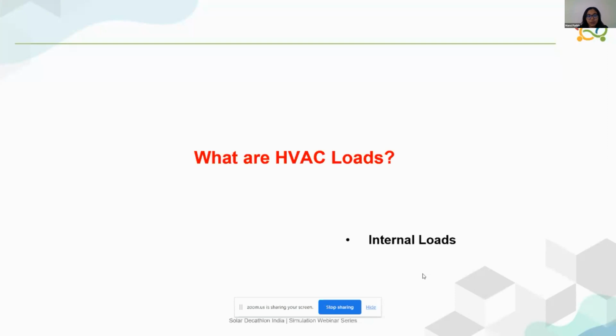In most parts of India, space cooling is predominant in buildings considering our climate conditions, so we specifically require cooling loads. Cooling load is the rate at which sensible and latent heat must be removed from the space to maintain constant space temperature, that is the set point temperature or dry bulb temperature and humidity in a particular space. So those are called HVAC loads, or specifically in the Indian climate, we would call it cooling loads, since climates like Delhi or Ahmedabad would specifically require a lot of cooling across the year.